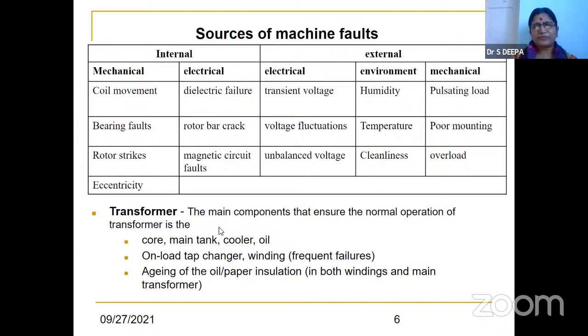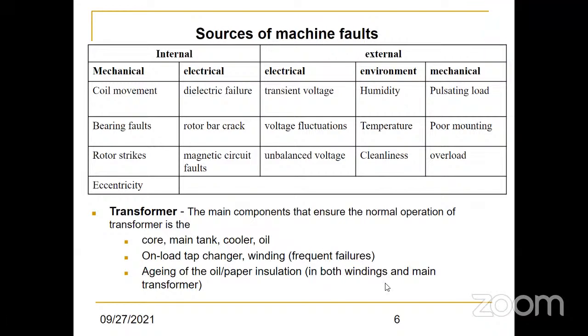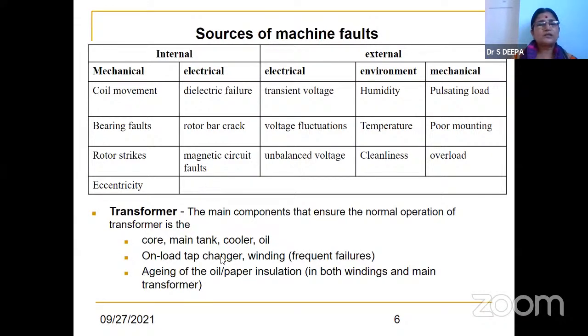Next is the transformer. The main components that ensure the normal operation of a transformer are the core, main tank, cooler, and the oil, and the on-load tap changer. They will not change the taps often, because frequent tap changing will cause the joints to heat up and there will be some disconnections, and because of that there will be some fault. Winding failures are frequent. Aging of the oil or paper insulation in both winding and main transformers. These are the types of faults that will occur.